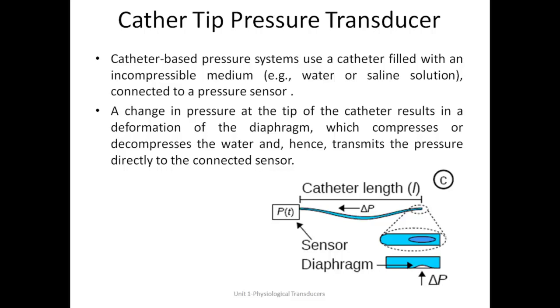This catheter tube is used to measure pressure inside the body. We take a catheter tube and fill it with an incompressible medium, then seal it from both sides. Incompressible medium means a fluid, either water or some saline solution, whose volume does not change. This is very important: the medium filled inside the catheter tube has to be incompressible. So we have a catheter tube sealed from both sides, completely filled with this incompressible medium.